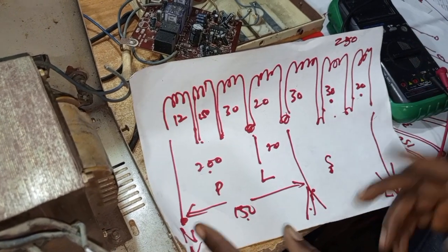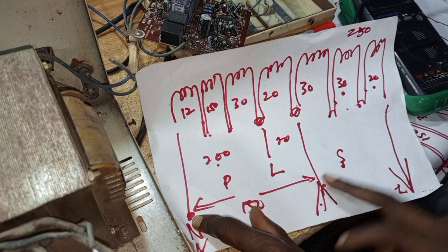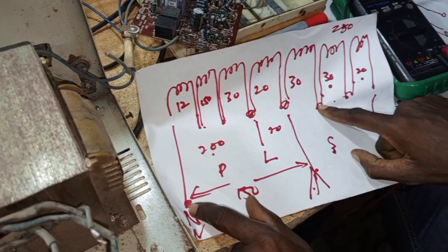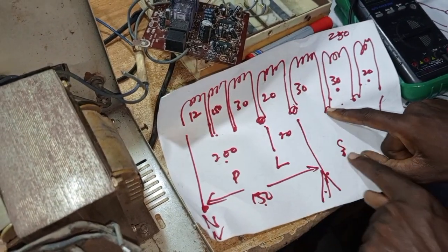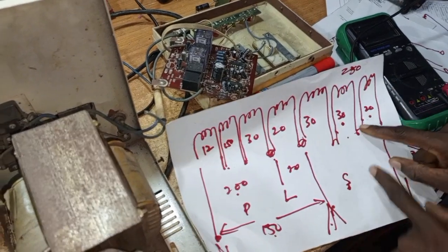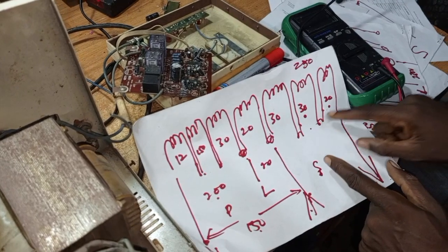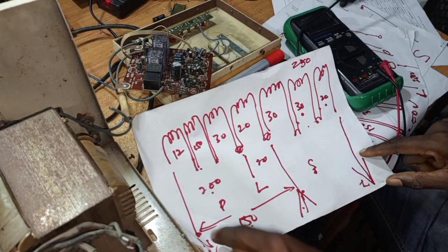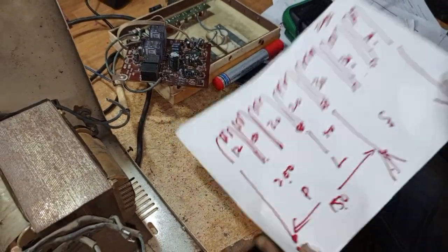Let's assume my input voltage is 150. If I needed 180 volts, I will put my secondary output line to this place, because it's 150 plus 30 — I will get 180 here. If I need 210, I will come to this place. If I need 230, I will put it at this place. But the neutral remains unchanged — I do not change the neutral. So this is an example of an auto transformer.